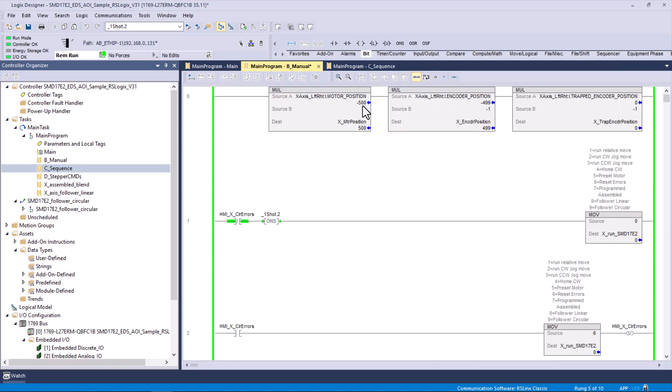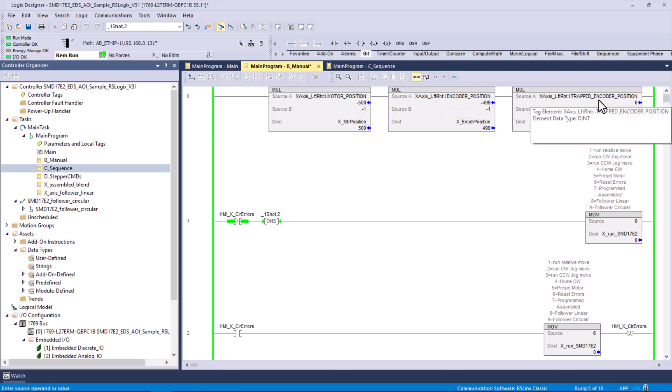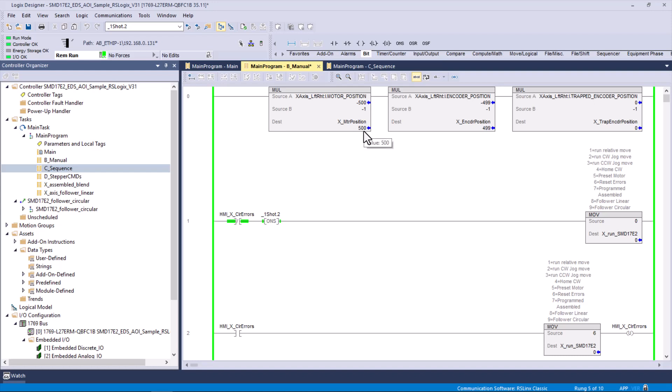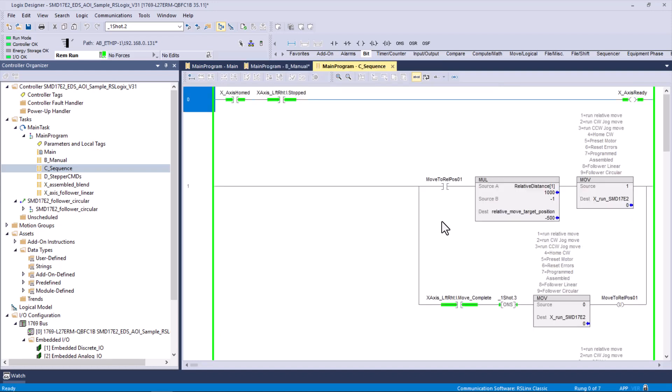The reason this isn't on anymore is because it moved the 500 offset, and I can show you that by going up here. Motor position, encoder position, trapped encoder position. I don't really need that. I'm using this to convert the motor position and the encoder position back to a positive number. I'm not really using this yet. This is just logic I threw in there, and if I was writing a program for the sake of the maintenance people, I would probably use positive numbers for all of my functions, but I have to convert it to a negative number before I send it to the axes.